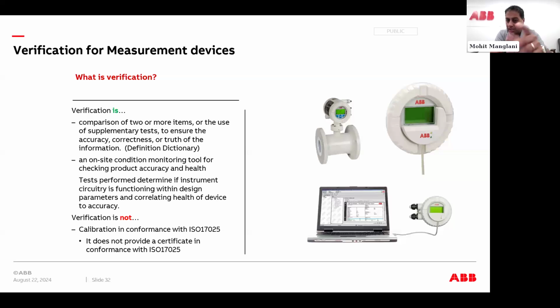We offer the capability such that you can connect a device on the outside of our device, this is specific to ABB, such that we can test the device to the standards in which we manufactured the device. And then assuming that's within certain tolerances that we've set, you can get a nice certificate that says, hey, this thing is accurate, it works, and it's healthy. Within that same tool, you're able to do predictive maintenance if you have degradation coming over time. This is called verification. This is not calibration. Verification is not a calibration.